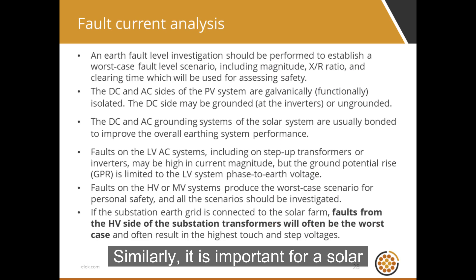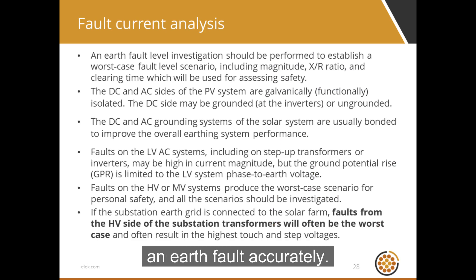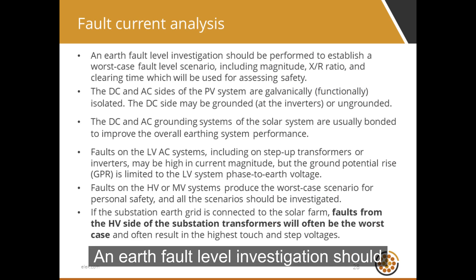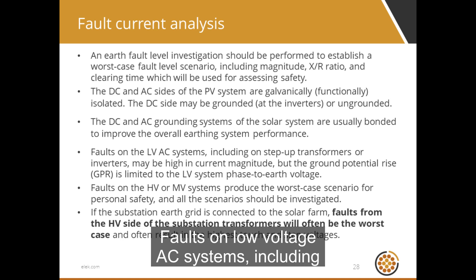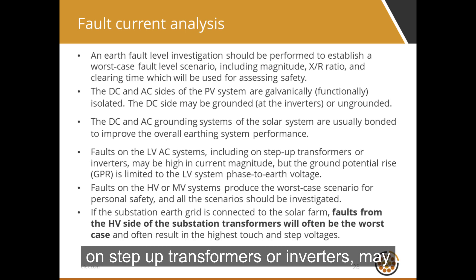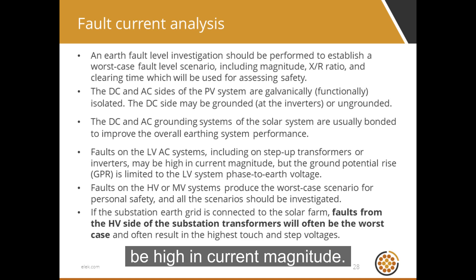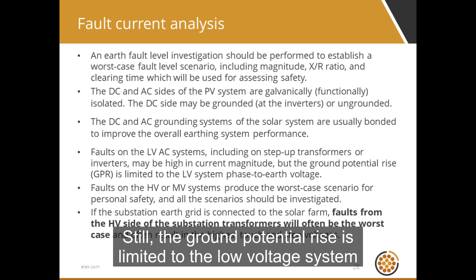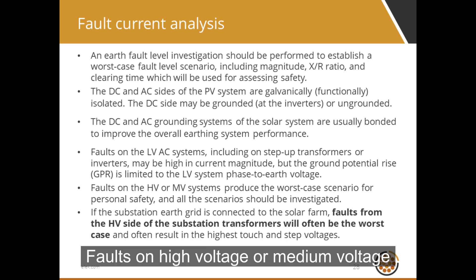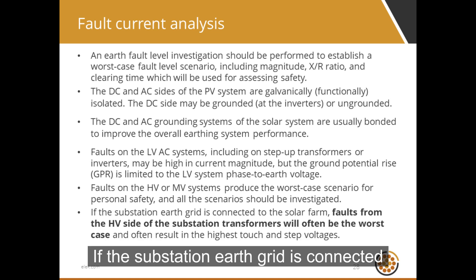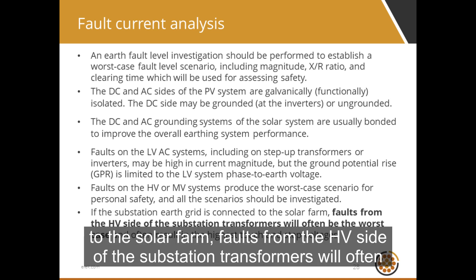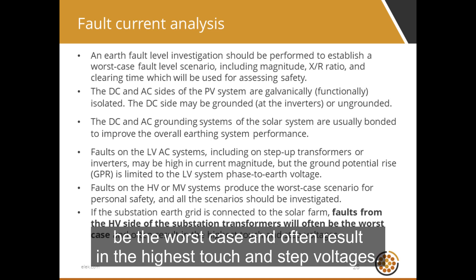Similarly, it is important for a solar farm to determine the fault currents during an earth fault accurately. An earth fault level investigation should be performed to establish a worst-case fault level scenario. Faults on low-voltage AC systems, including on step-up transformers or inverters, may be high in current magnitude, though the ground potential rise is limited to the low-voltage system voltage. Faults on high-voltage or medium-voltage systems produce the worst-case scenario for personal safety, and all scenarios should be investigated. If the substation earth grid is connected to the solar farm, faults from the HV side of the substation transformers will often be the worst case, resulting in the highest touch and step voltages.